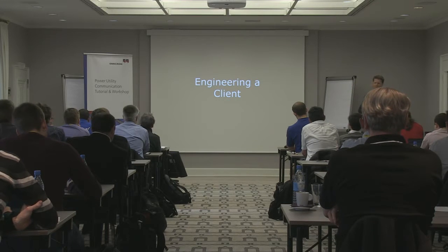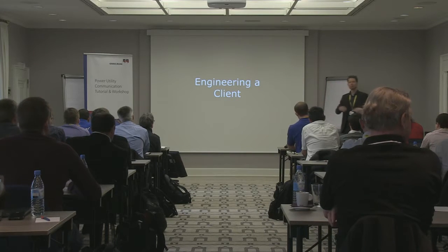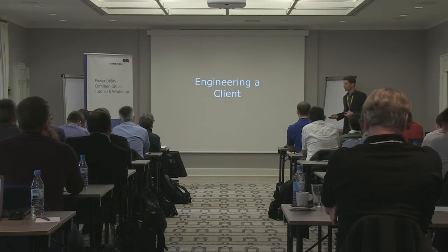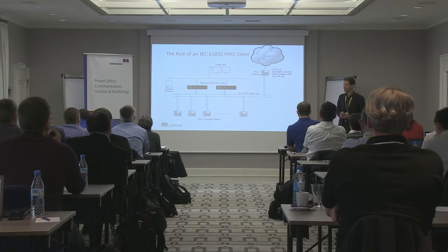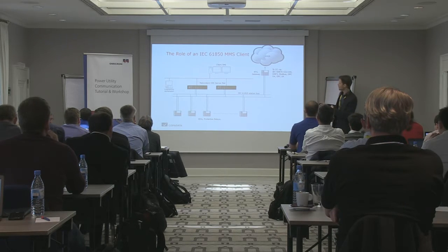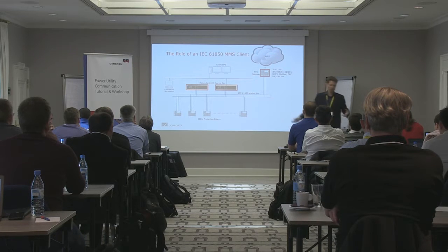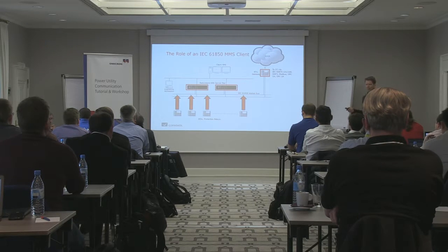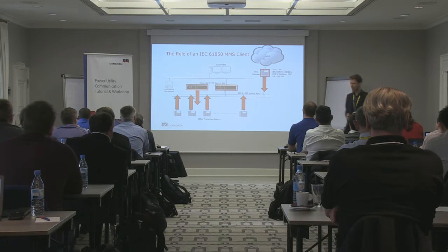Now we know about where the data comes from and which data we need. But how to do the engineering of such a client? Again, we have this architecture. And who or which devices do we understand as IEC 61850 clients? It's, of course, these parts — although the HMI server is called a server, in terms of 61850 it's a client. We get the data from the 61850 servers and we write the data from the client towards the servers.